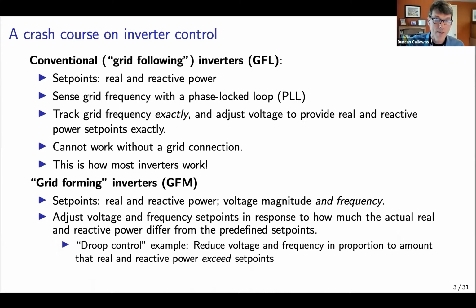A grid forming inverter, on the other hand, has much more complexity in the control loops, where instead of sensing grid frequency and just following that exactly, it produces its own frequency set points, but then makes adjustments to that frequency in order to synchronize itself with the grid. It sounds like that might be the same, but that subtle difference means that you can actually regulate frequency with a grid forming converter. And as the name suggests, you can actually build up a grid without a connection to a larger synchronous grid. You can build up a grid with a collection of grid forming inverters.